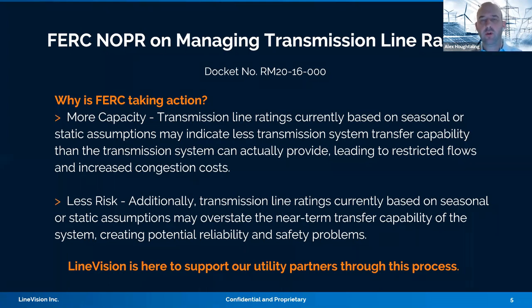But risk is also a factor - the ability to use advanced line ratings in a smart way to make sure that for those few instances where advanced line ratings actually fall below static ratings, we're not doing damage to our conductors. Advanced line ratings can help both with the upside and the promise of more capacity, but also address resiliency and the need for a strengthened, strong, reliable grid.